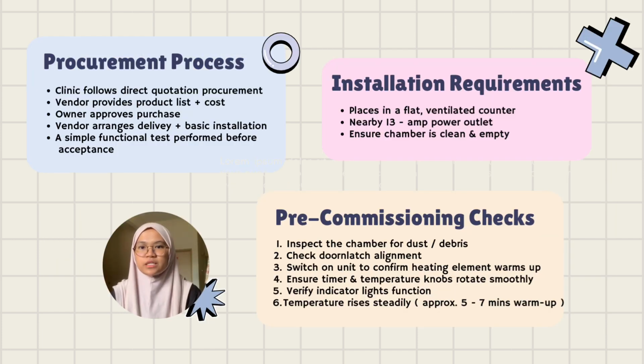For procurement, the clinic procures the sterilizer through direct quotation. The vendor provides a quote, the clinic approves, and the unit is delivered and installed. It is placed on a flat ventilated counter with a 13A outlet, and the chamber must be clean. Pre-checks include inspecting the chamber, door latch, heating function, timer, and temperature knobs, and indicator lights. The unit warms up in 5 to 7 minutes.